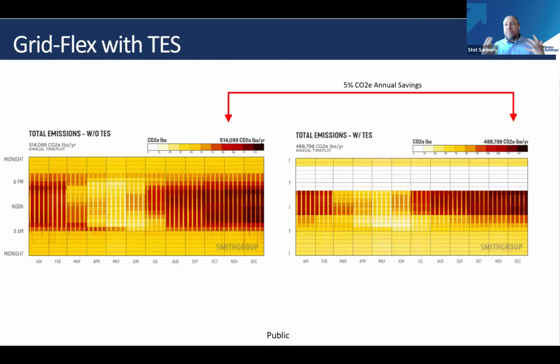On the emission side, thermal storage also gives you that benefit of, even with a really dumb clock that says, hey, charge this tank at these hours, turn the heat pump off on these hours, even the most basic control sequence can see 5 to 10% CO2 or greenhouse gas emission savings just with that. So that's not even taking into account smart controls or AI or any other buzzword in the marketplace. Thermal storage gives you that flexibility to see immediate reduction with your system and self-utilize your own electricity generation with PV.